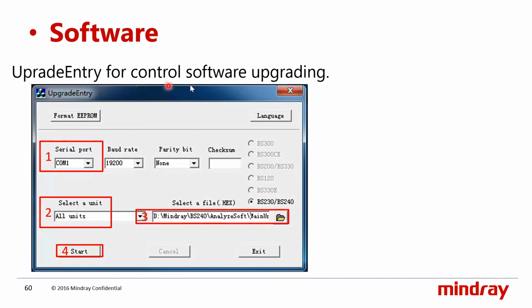Upgrade entry for control software upgrading. Whenever you are upgrading existing software, make sure there is an upgrade tool on the D drive, Mindray. There you can find this upgrade tool. Make sure the serial port is selected, and all the modules, all units, and the destination folder. You have to select the destination folder and start. Okay.